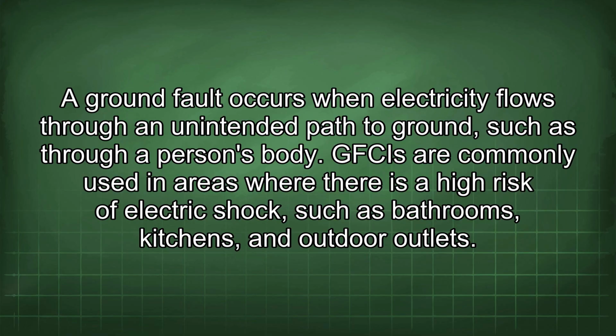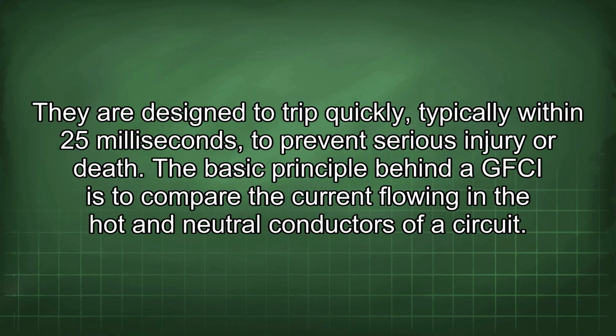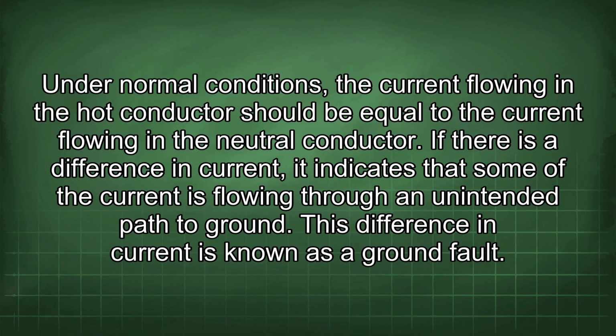A ground fault occurs when electricity flows through an unintended path to ground, such as through a person's body. GFCIs are commonly used in areas where there is a high risk of electric shock, such as bathrooms, kitchens, and outdoor outlets. They are designed to trip quickly, typically within 25 milliseconds, to prevent serious injury or death. The basic principle behind a GFCI is to compare the current flowing in the hot and neutral conductors of a circuit. Under normal conditions, the current flowing in the hot conductor should be equal to the current flowing in the neutral conductor. If there is a difference in current, it indicates that some of the current is flowing through an unintended path to ground. This difference in current is known as a ground fault.